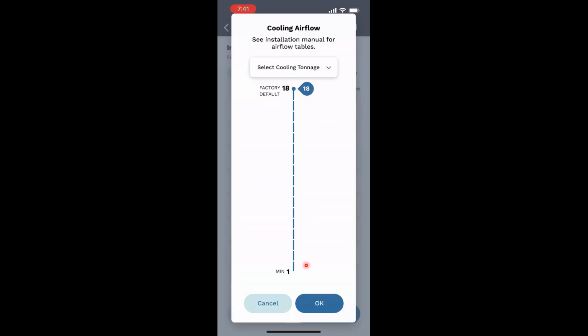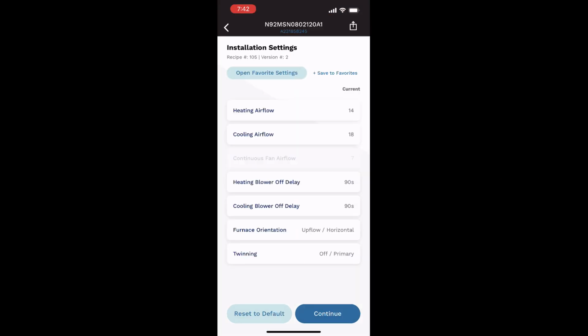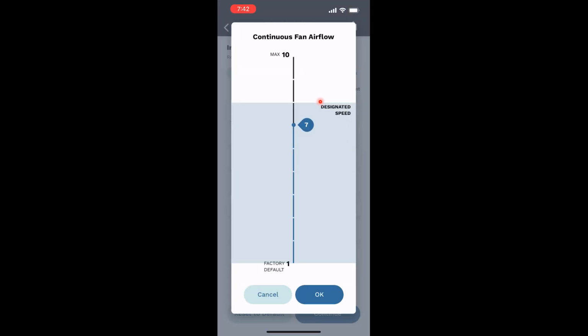And in cooling, you can go as far as you want to, 1 to 18. Let's go back real quick. I wanted to show that you can select the tonnage on the cooling too. So then you have continuous fan and you have your different speeds, which you can select 1 through 10. And that will help you dial in. If you're doing a continuous airflow, you can dial that speed in.